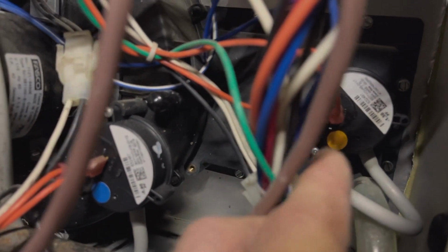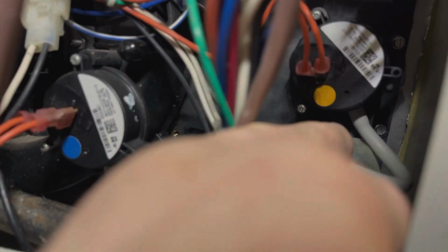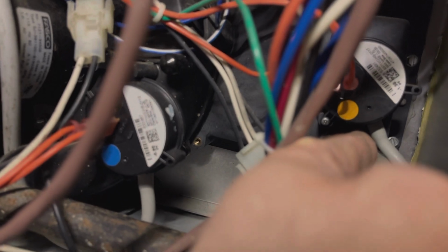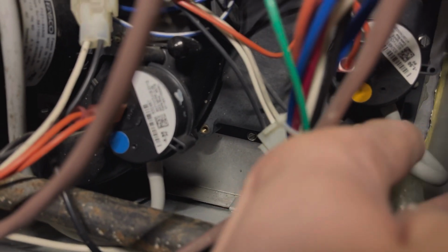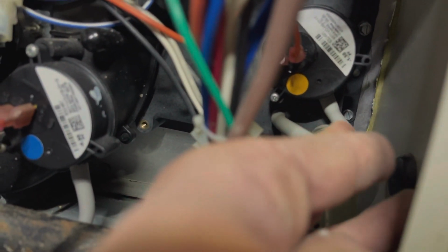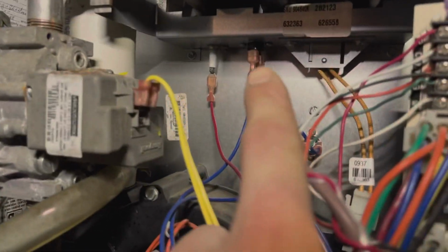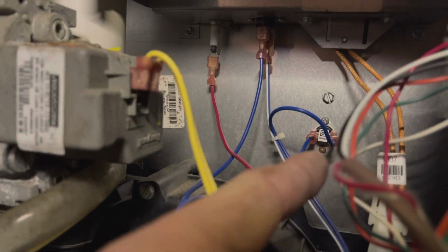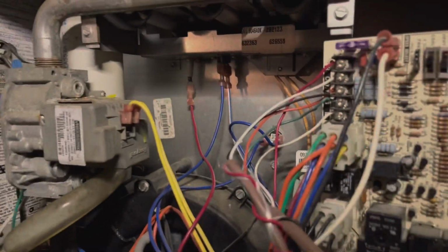And I forgot to mention these little tubes. That's your common problem with them. They can get clogged up. So you could pull those off, and you can make sure that you can blow air through them, and it goes through both ends. When I was talking about testing these, I took off these and I tested them with a multimeter for continuity, and depending on the side of them, it shows L or F.